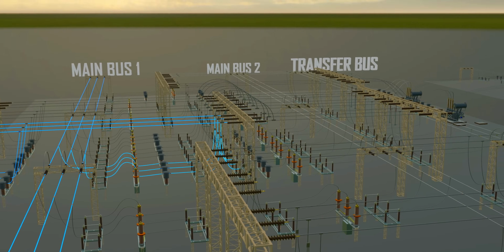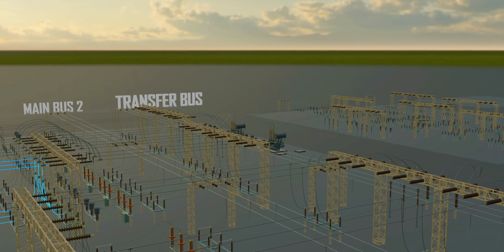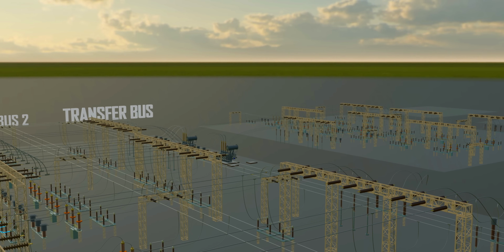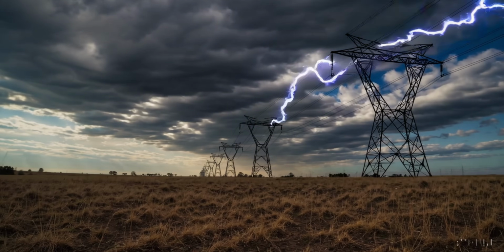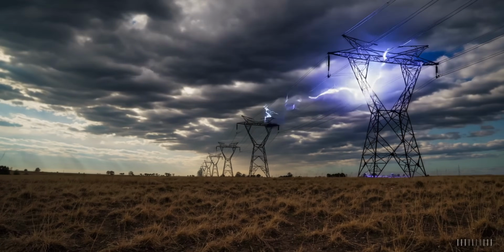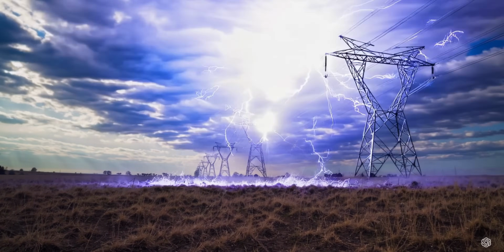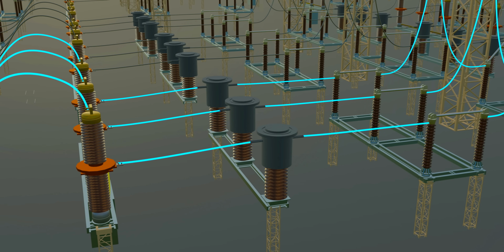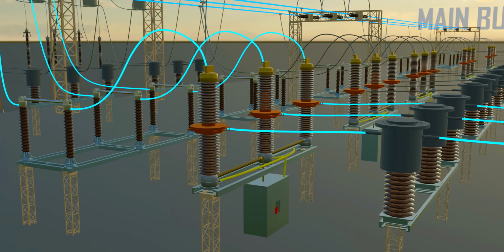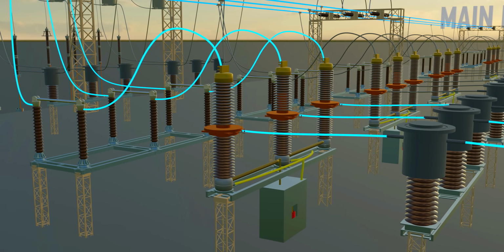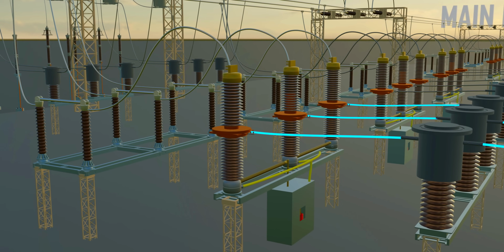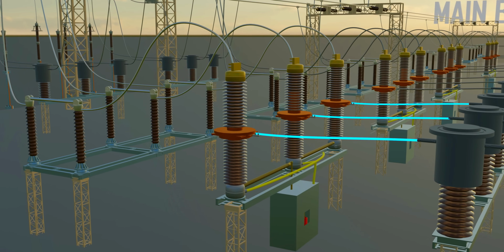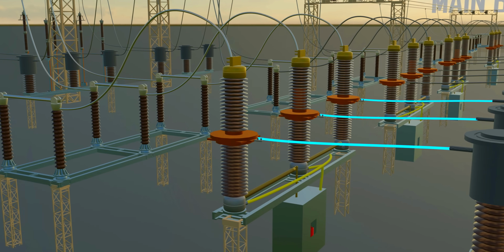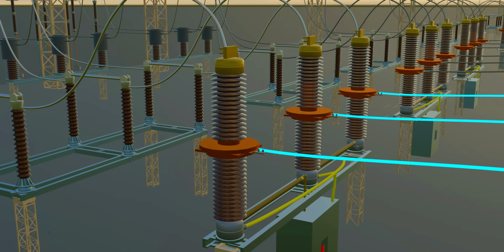Let's take a fault scenario to understand how the system works. Imagine a line from the switchyard extending outwards, and a conductor falls to the ground, creating a serious line-to-ground fault. The current transformer instantly detects the surge in current, signaling a fault. It sends a command to the circuit breaker, which trips and cuts off power beyond that point to prevent further damage. Although the circuit breaker disconnects the line, there's one more challenge.